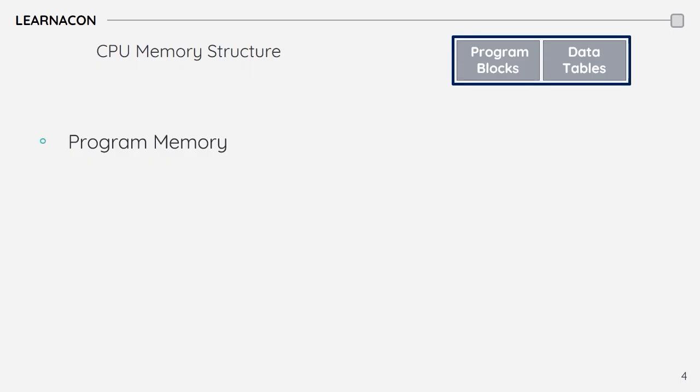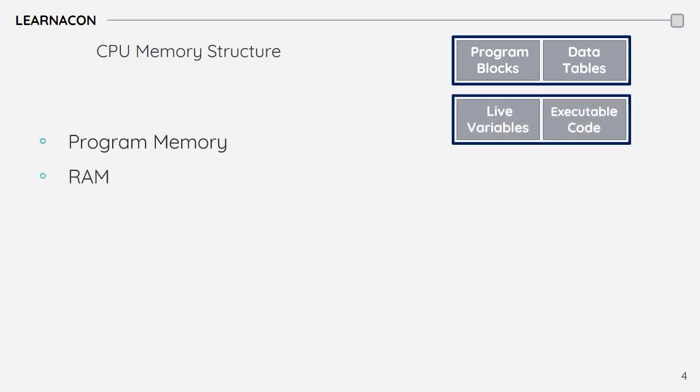By changing the CPU mode to run, the operating system will transfer a copy of executable parts of the program into the RAM, allocate memory for variables, and initialize them. Keep in mind that power cycling or restarting the controller will erase the content of the RAM. That means if the CPU goes to stop, all RAM variables will be reset. Most often, you cannot change the size of the RAM in a PLC, so make sure to pick a CPU that can fit your application.